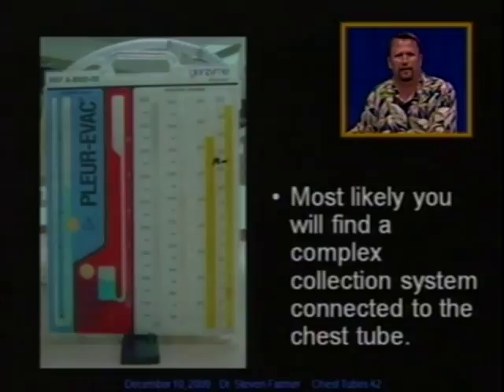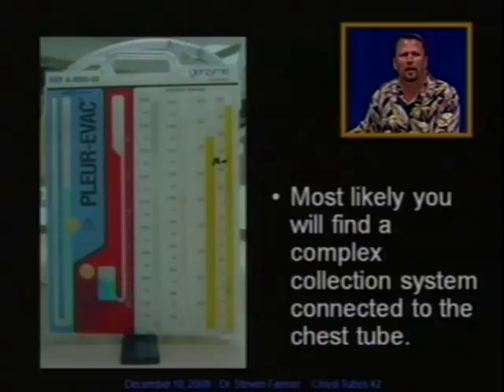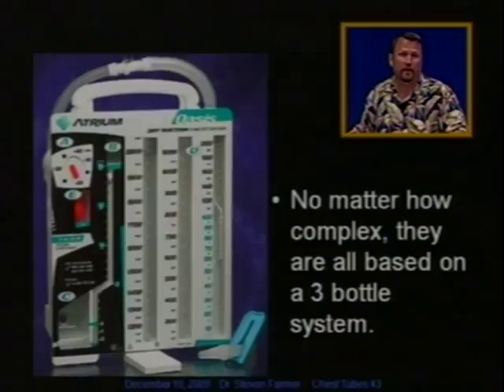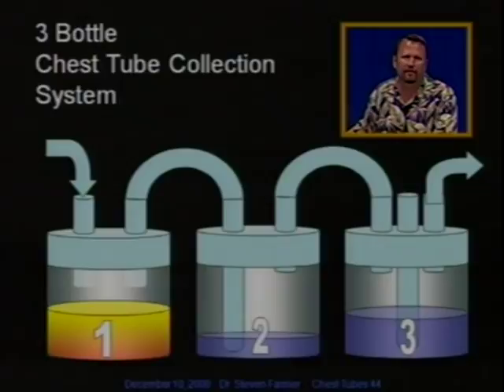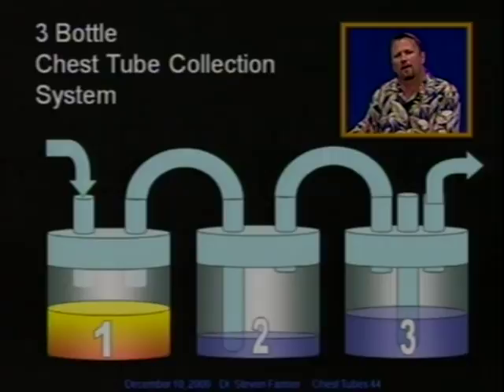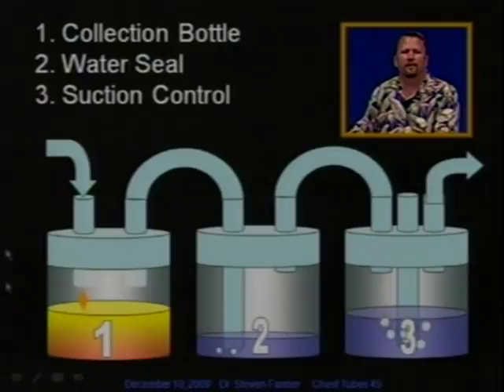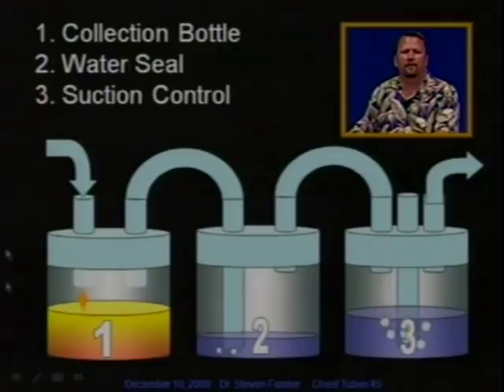In a hospital, you'll most likely find a very complex collection system connected to the chest tube. No matter how complex, they are all based on a three-bottle system. In this three-bottle chest tube collection system, bottle one is the collection bottle — we can see fluid from the chest tube dripping into it. Bottle two is the water seal. Bottle three is suction control, which ensures a consistent and precise amount of suction is applied to the system.